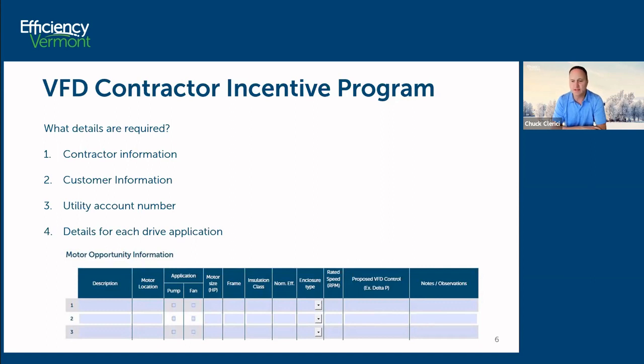And then this is important, the second to last column, the proposed VFD control. How do you propose to control the drive? The most typical are delta T and delta P pressure. There could be instances where you might want a fixed drive setting of, say, 50 Hertz. We don't love those, but there are instances in the marketplace where that is the appropriate control strategy. And then in the notes column, just put some rationale about why you're choosing the proposed VFD control.